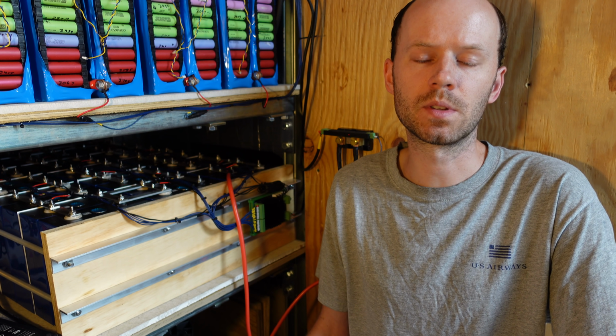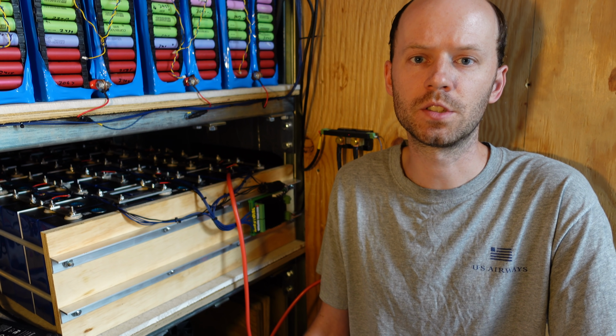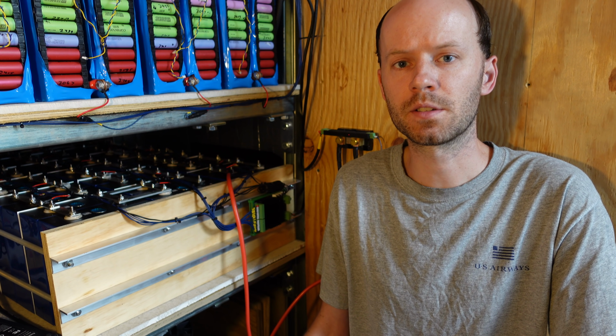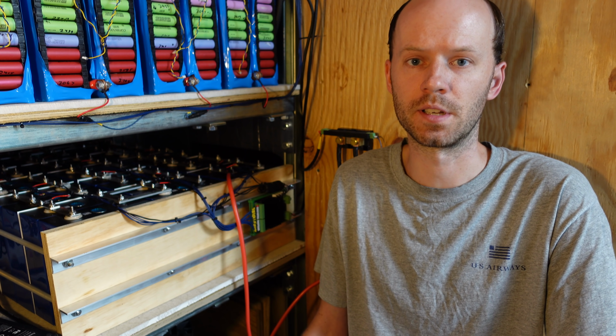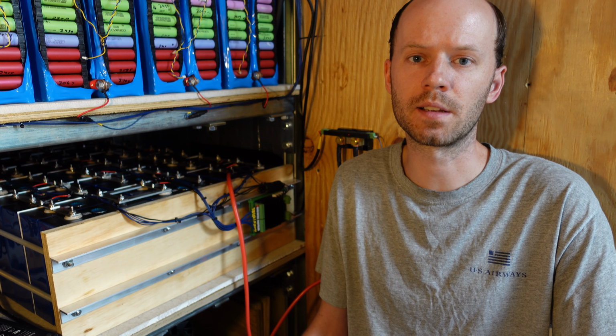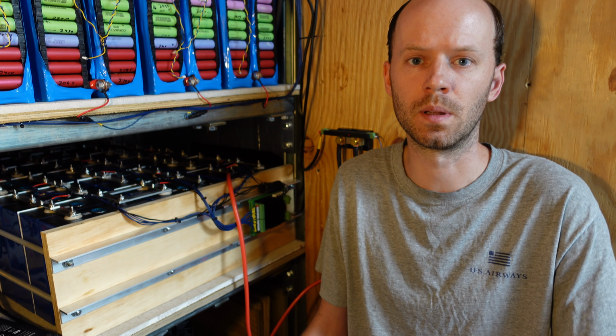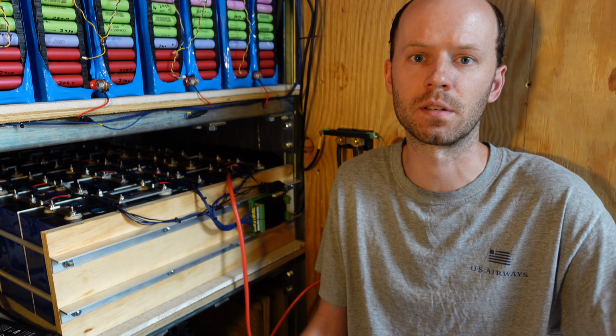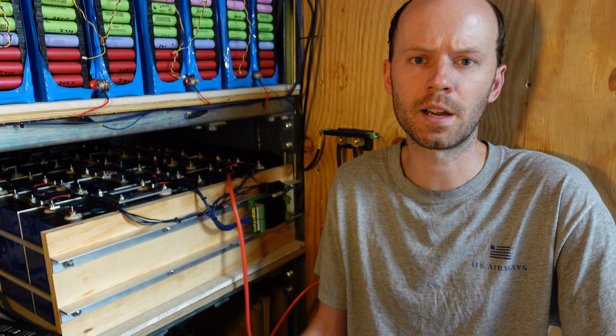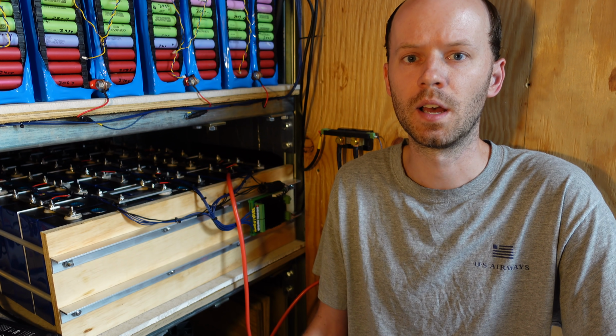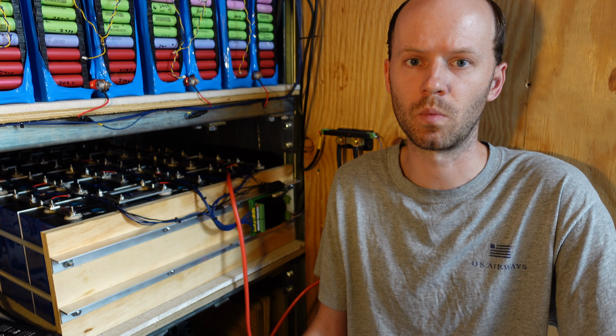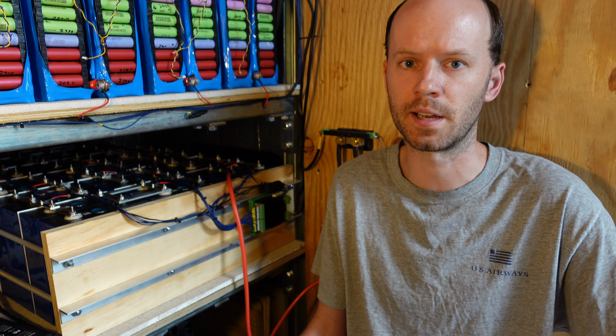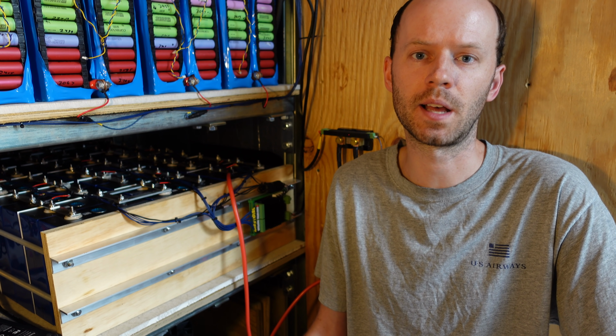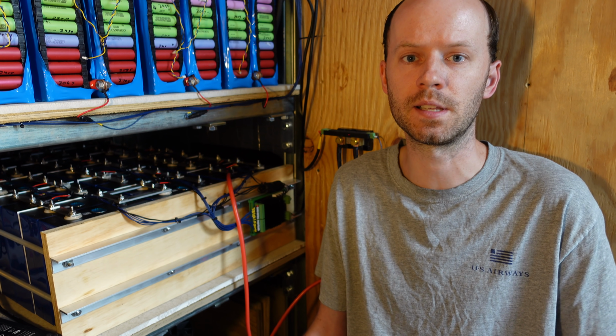Keep in mind this test was only done around a 0.12 C rate, and these batteries are rated for around a 1 C rate charge and discharge. I did the test around 3000 watts because that's a fairly typical load I expect to see these batteries at once they're in service. In fact, that's probably on the higher end - the load's going to be significantly lower, since I won't be pulling 3000 watts from one battery bank of multiple at a time. I do expect these batteries to last a very long time, and hopefully we see that over the next couple of years.